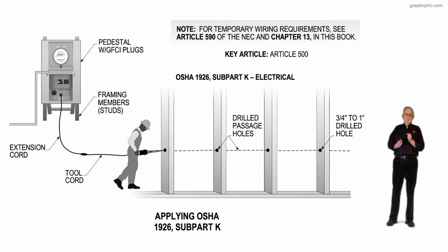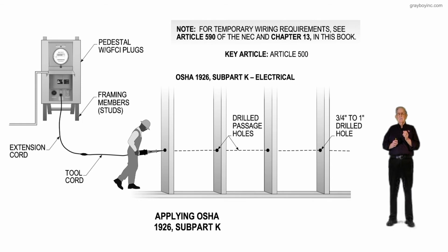So we're using a 500 series here because we're using 590. So those are special articles that deal with special rules based upon what's taken place. Now let's just say all the construction has been performed by OSHA 1926 Subpart K and the NEC starting with 590 and other pertinent sections, and the equipment and wiring has been accepted by the facility, approved by the authority having jurisdiction. Then we would look at NFPA 70B for rules, because that pertains to maintenance.